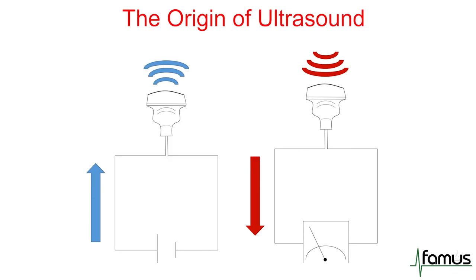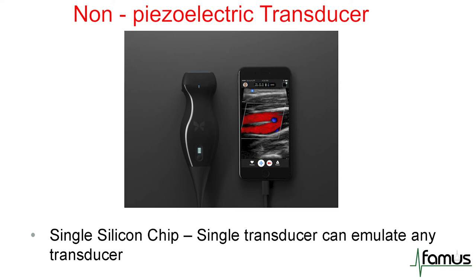The next slide shows how ultrasound waves are generated. We have a piezoelectric element, or crystal, on top of our transducers, and if we put electricity — a current — onto these crystals, ultrasound waves are generated. Once the ultrasound waves are reflected and coming back to our crystal, a voltage is generated which the machine can measure. There are now newer technologies using non-piezoelectric transducers; for instance, a device with a single silicon chip where one transducer can emulate any point-of-care ultrasound transducer.